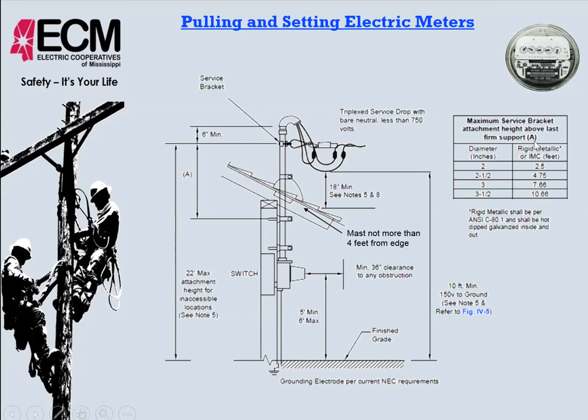So we look over here at this chart to the right. For 2-inch pipe, 2.5 feet from where our service entrance is going to attach to the conduit. That attachment is 6 inches from the top of the pipe. Okay, so if we have 2-inch rigid conduit, not EMT or anything like that, but rigid conduit, it's 2-inch. This can't be any more than 2.5 feet from this point to where our service entrance is, and there again the service entrance attaches to the pipe at 6 inches below the top.